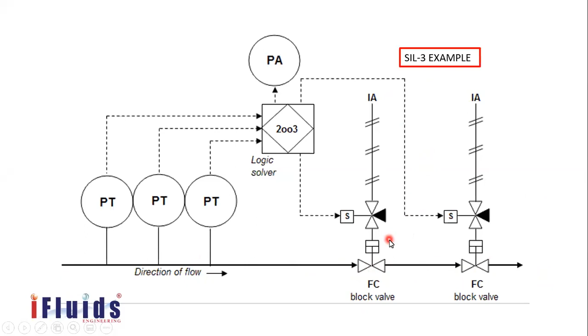For example, in a furnace, I am having a fuel gas system going into the furnace. By any chance, if my flame got tripped, or because of low pressure it got tripped, it will close, block and bleed. You have 2 blocks and you have bleed also. Suppose there is no flame, your fuel gas can pass and go, and if you go for ignition, it will go for explosion. There they will have 2 XVs, and another one in between, there will be a vent. Even if it passes, it will go to the flare or a safe place. So both valves will not fail at the same time and the vent also opens. So ultimately, the probability of fuel gas going to the furnace becomes less. Okay, this is the principle here.